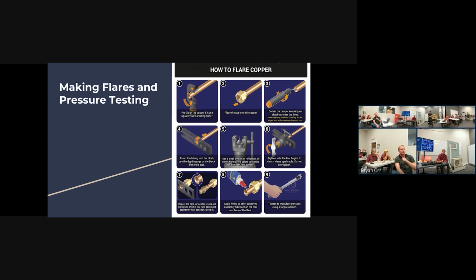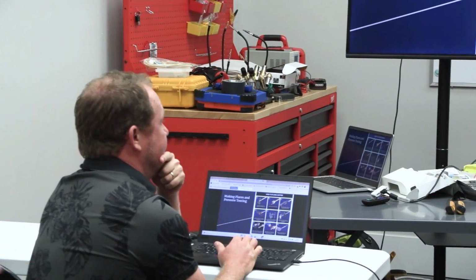So again, with a torque wrench, it's always really important that you hold it by the handle. If you change where you hold it, you're actually changing the pivot point and changing the end torque that you're producing. All right. And this is probably the number one reason that we get called out to just random ductless systems. There's a lot of people installing their own or calling their maintenance guy to install a ductless system, and leaking flares are probably the number one reason we get called out to a ductless system. So, system low on refrigerant.